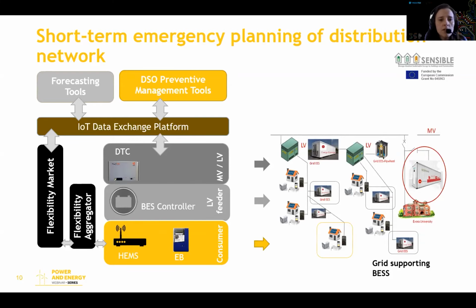So in this case, we have here a storage device and also a bigger one for the medium voltage consumer. And in the case of the public low voltage distribution network, we have also smaller units that provide support to these main grid forming units. So with this system, we can create two low voltage islands, the medium voltage consumer and the low voltage public distribution network, or we can island at the medium voltage level and have this medium voltage island supported by the different storage devices.